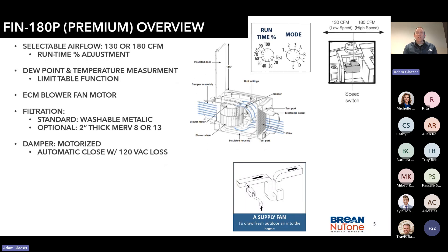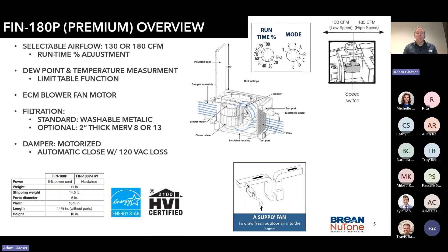The unit is very versatile. It has either 130 or 180 CFM capabilities. It has dew point and temperature measurement — we'll get into that further as we go along. It has intelligence, and that's really important. It also has an ECM blower fan for more efficiency and quieter operation. It has a standard washable metallic filter and is available up to a MERV 13 filter, depending on user needs.